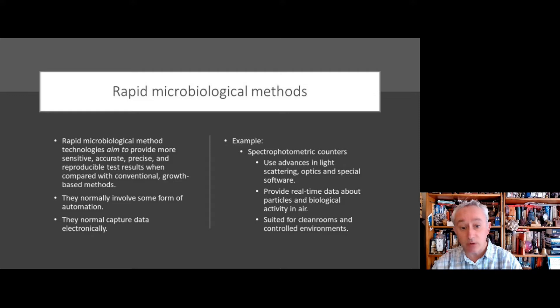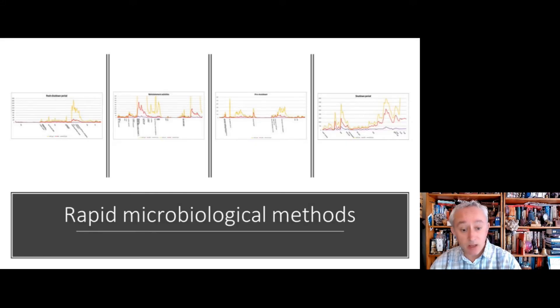Okay, so here is some data from these particle counters, and this is data that I actually gathered myself. With these charts, biological readings or bio readings are in red, particle counts are in yellow, and the objective of these four charts is showing the status of a clean room going through different states.